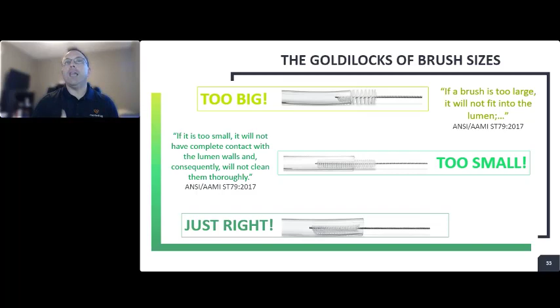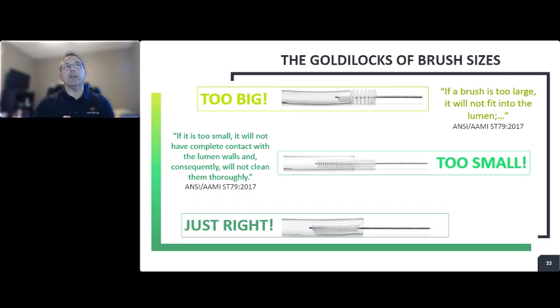Now, the good news on this is, when I talk to our brush manufacturers on this, they say, listen, you don't have to be perfect anymore. It's not about being 2 millimeters larger than the channel. It's just about being larger. There's a large difference between smaller or too small and getting to too large. So if we're 1 millimeter larger, it's a very small measurement. We're in good shape. 2, 3, we're okay. The whole key is being larger. And that's what most of our brush manufacturers are telling us today.